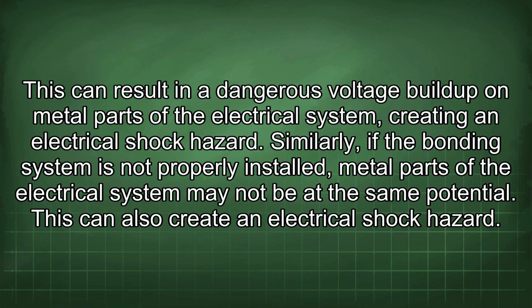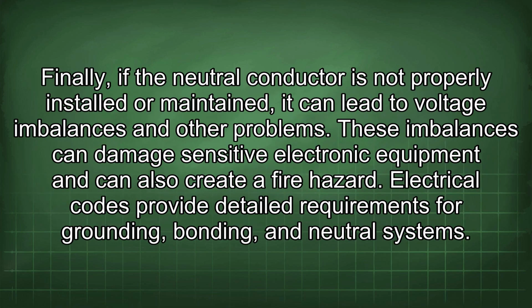This can result in a dangerous voltage build-up on metal parts of the electrical system, creating an electrical shock hazard. Similarly, if the bonding system is not properly installed, metal parts of the electrical system may not be at the same potential. This can also create an electrical shock hazard. Finally, if the neutral conductor is not properly installed or maintained, it can lead to voltage imbalances and other problems. These imbalances can damage sensitive electronic equipment and can also create a fire hazard.